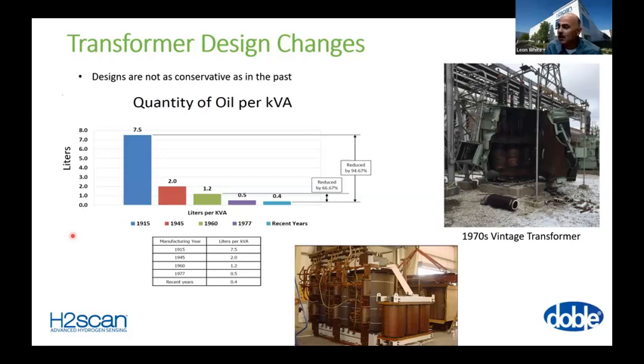I happened to be working with a customer, probably 10, 12 years ago, that had a transformer failure at a power plant. The picture on the right is a transformer that was an auxiliary transformer at a power plant, and prior to its failure had no history of problems. The point of putting it on this slide is that this was a 1970s vintage transformer. You can see how small the windings were for how big the tank is. Of course, today's designs wouldn't have near that much space.